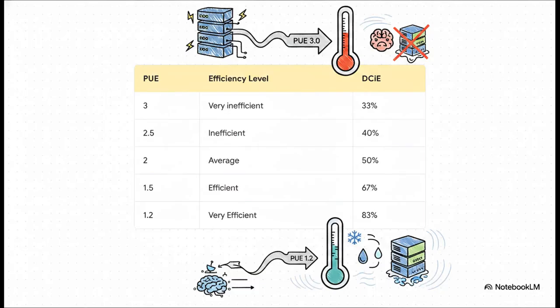When you map these PUE levels out, the contrast is super stark. Up at a PUE of 3.0, you're looking at a very inefficient facility, meaning only a tiny fraction of your expensive power is actually doing computing work. But to hit that top-tier, very efficient 1.2 level at the bottom, facilities absolutely have to rely on rigorous, constant control of temperature and humidity. Without insanely accurate heat monitoring, hitting that 1.2 is pretty much impossible.